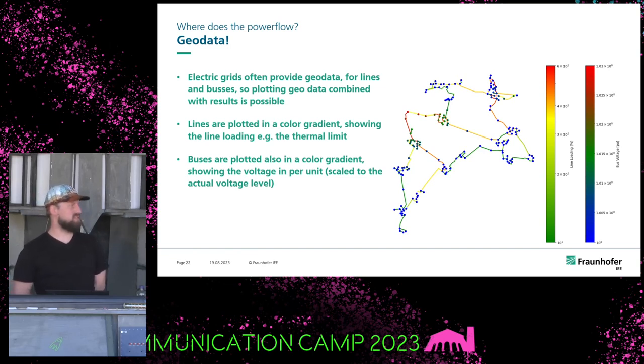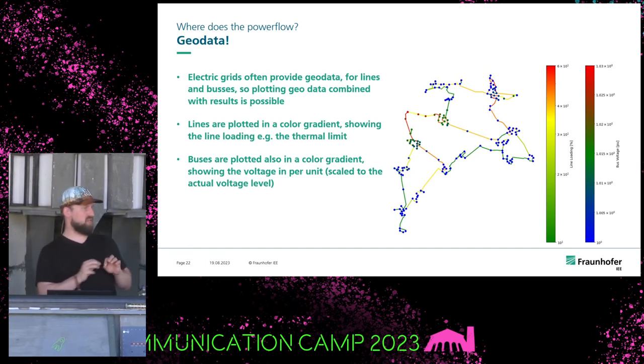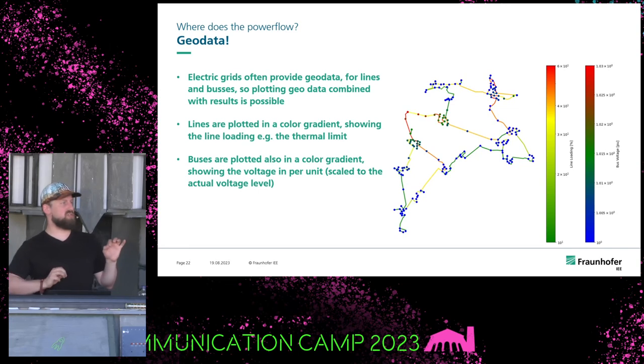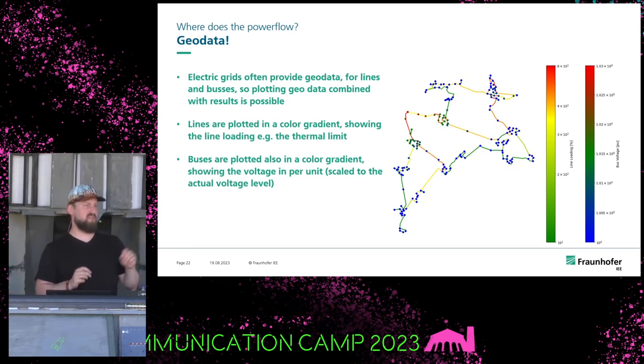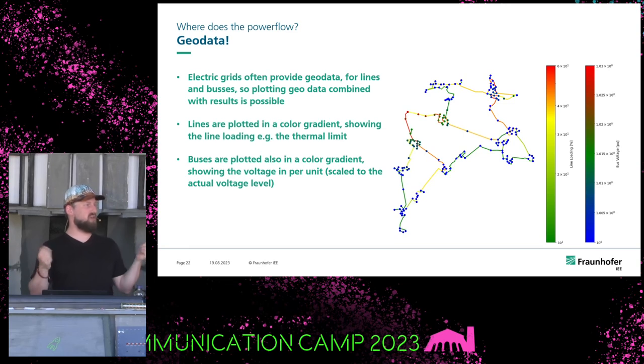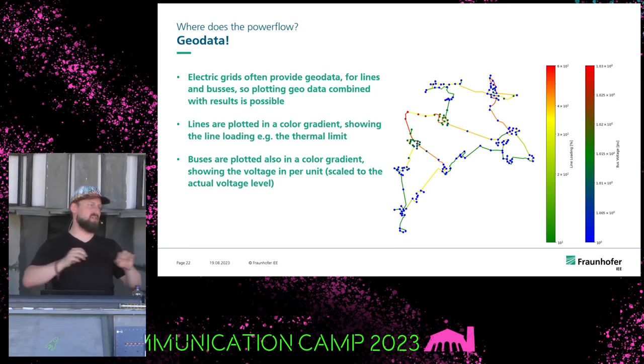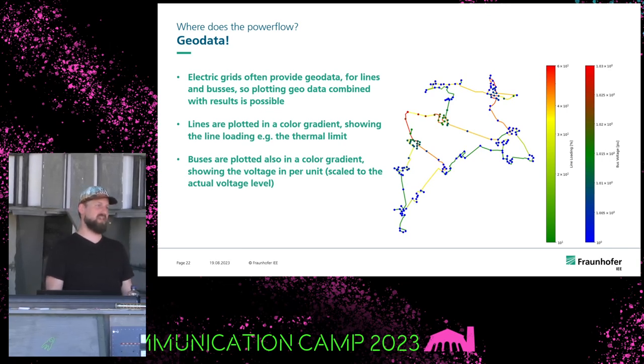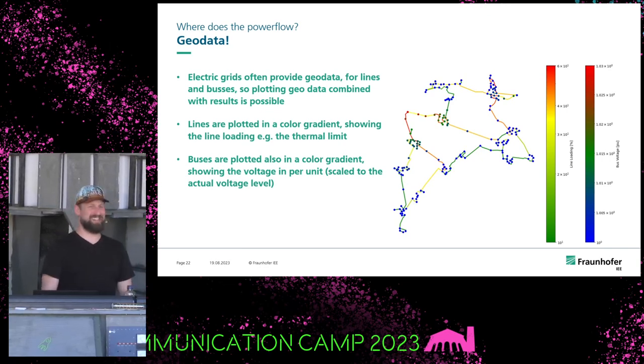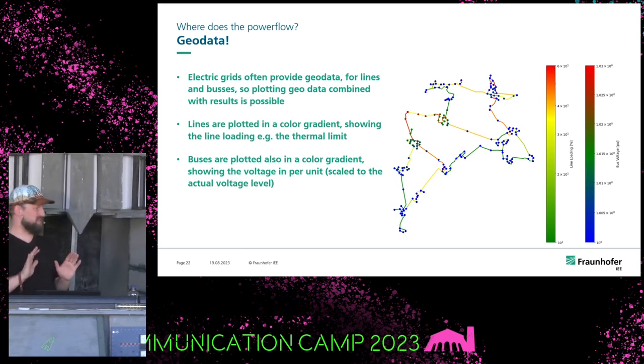Red means overloaded for the lines, and for the buses you have a per unit voltage level. So you have multiple factors in your power network. On one hand, the power lines shouldn't get too much current. If they do, they tend to get hot, and if they get hot they get longer and start to sag. And if they touch anything, you have a big problem. So this is mainly the part you want to keep track of.